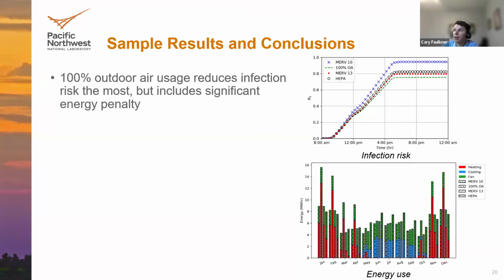So quickly, some results and conclusions from this. As I mentioned before, we compared 100% outdoor air usage against MERV 10, MERV 13, and HEPA filters. This plot on the top right shows the probabilistic infection risk that we calculated for one of the sets of scenarios from the study, where the y-axis shows the probabilistic predicted number of infections, where 1.0 is predicting about one infection to occur that day. The results showed that 100% outdoor air led to the least infection risk compared to the other methods, but had a significant energy penalty, especially during the cold winters of Denver in this study. I'll talk more about that in a second.